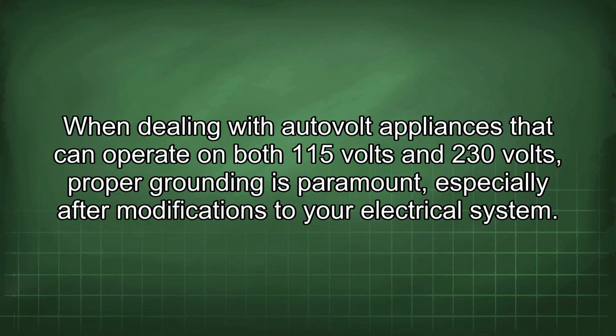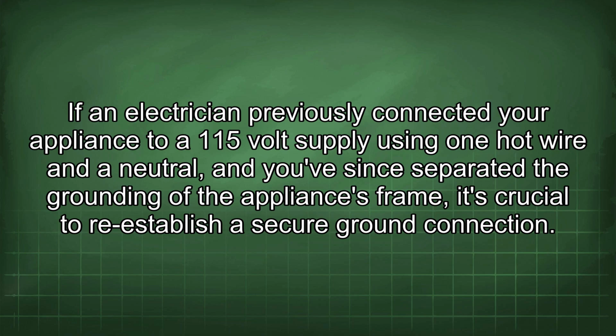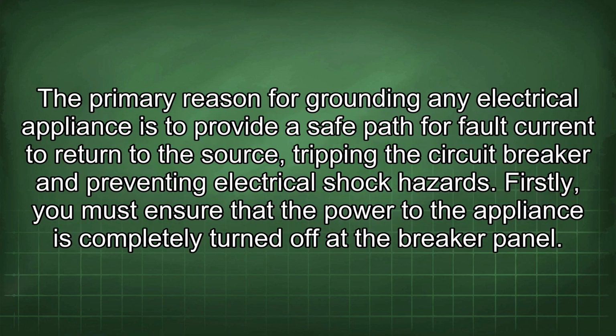When dealing with Autovolt appliances that can operate on both 115 volts and 230 volts, proper grounding is paramount, especially after modifications to your electrical system. If an electrician previously connected your appliance to a 115 volt supply using one hot wire and a neutral, and you've since separated the grounding of the appliance's frame, it's crucial to re-establish a secure ground connection. The primary reason for grounding any electrical appliance is to provide a safe path for fault current to return to the source, tripping the circuit breaker and preventing electrical shock hazards.